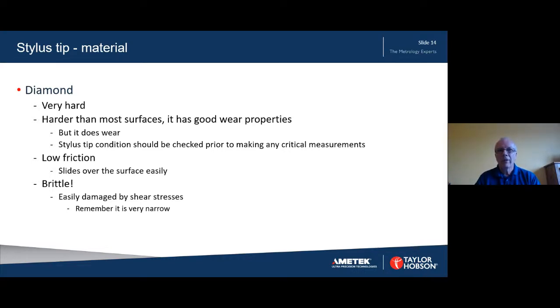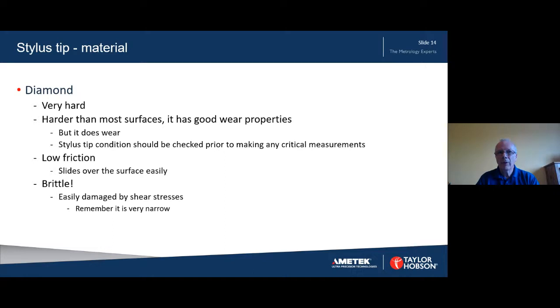Stylus tip material — the choice of material is important. Diamond is a really good choice for a number of reasons. Firstly, it's extremely hard and so has good wear properties. Nevertheless, it does wear, so the stylus tip should be checked prior to making any critical measurements. Diamond also tolerates being machined into small features and is ideal for making the small radius tips needed for surface texture measurement. Diamond has a low coefficient of friction, so it slides over the surface easily and causes minimal abrasion. However, it has to be remembered that diamond is brittle and can be easily damaged by shear stresses. This is particularly true of the stylus tip because there is very little material — it's only a few microns in diameter.